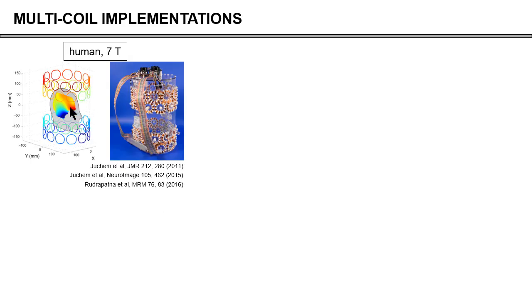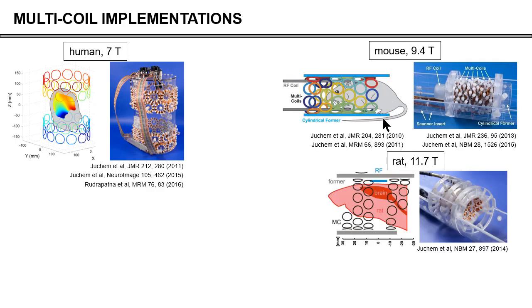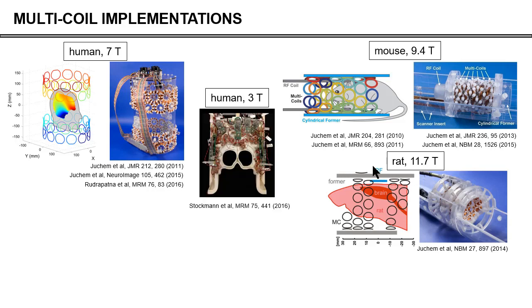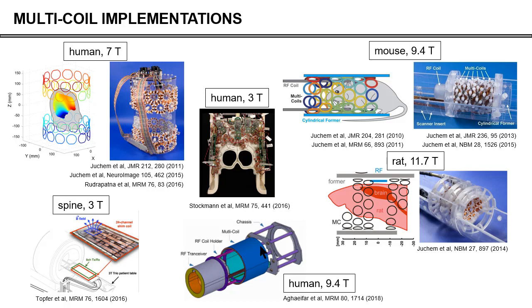We have used this multi-coil implementation on the human brain at seven Tesla, on the mouse head at 9.4 Tesla, and on rat brain at 11.7 Tesla. I'm very happy to see that other groups are now picking up this technology as well. The MGH group has applied it at three Tesla on human brain, combining the RF loop and the DC shim loop into one and the same loop, which is very efficient when it comes to space. Another nice application is a group using it for the human spine, incorporating these little DC coils in the patient bed, with really nice results. Very recently they've also used it on ultra-high field.